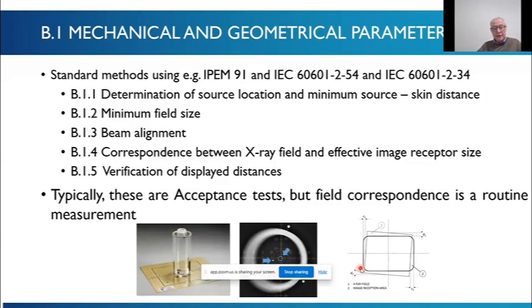So if we go on to the mechanical and geometrical parameters, which is the first set, so when you start to do QC, I think it's important to start with the source and how the source is installed, and how the geometry of the system is working. So this is a fairly typical test, so you probably see them in quite different protocols as well. For example, determining the source location and the minimum source skin distance, where you would use test objects of a certain length and then another test object of twice that length, and you image them at different distances to determine the source location. Or you look in the manual, or you look on the side of the X-ray tube to see if it's been marked, and if it hasn't been marked, ask them to mark it, for example.